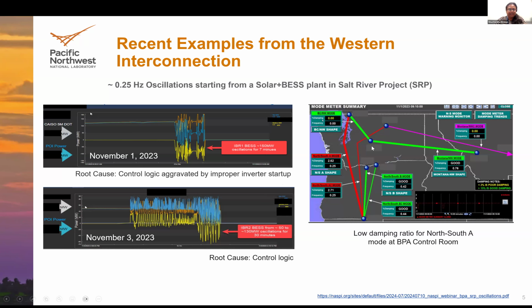And they saw that they have a mode monitoring scheme in place at their control room, and they saw that due to the presence of the forced oscillation, they saw underdamping issues in the North-South A mode, which is indicated here by these red lines. And so coordination was required among the different system operators to identify, okay, what I'm observing, is it really an underdamped natural oscillation that may lead to 1996-like outages, and so we need to take control actions, or whether it was a forced oscillation.